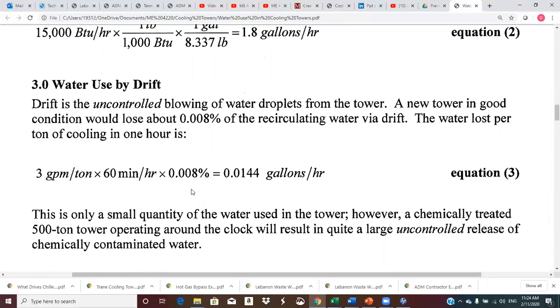Drift is the uncontrolled blowing of water droplets. And we said a new tower in good condition would lose 0.008%. And so we do a little math on this. The water loss per ton of cooling in 1 hour, or per ton hour, would be 0.0144 gallons per hour. So this is not a whole lot of water. However, if you run the math on, say, a 500-ton tower operating around the clock, it turns into a fairly large amount of uncontrolled, chemically contaminated water. So this has the bacteria and the chemicals and the minerals and all that stuff in it.